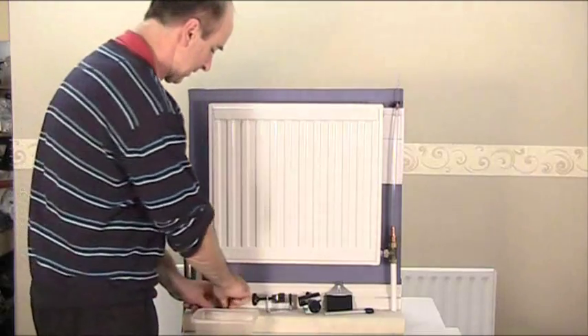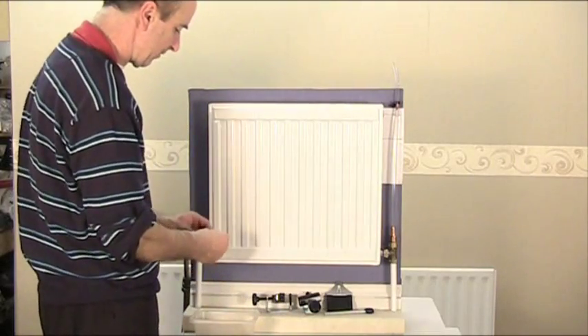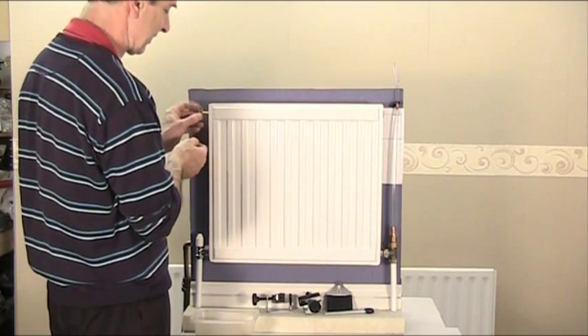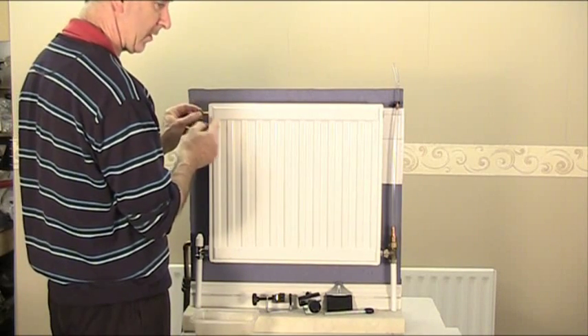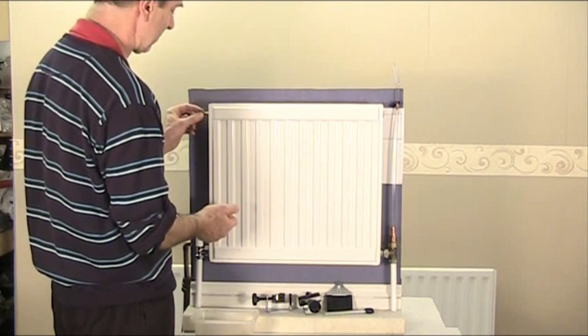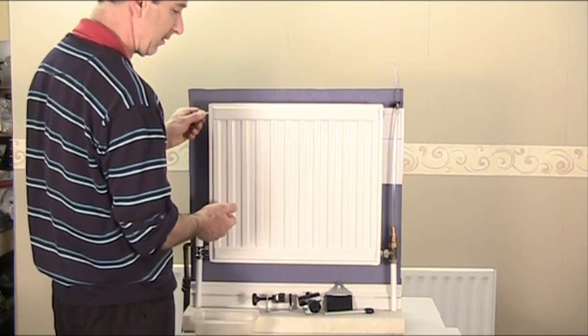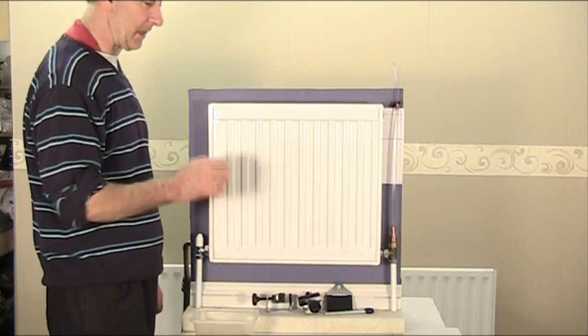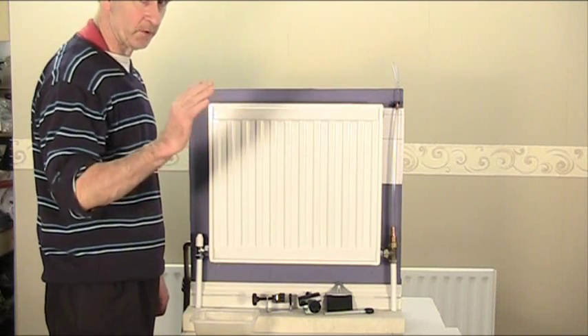So basically that's just a demonstration to show you what's happening when you are releasing air out of the radiator and the water is coming in. Now don't forget, it's a very important point that I mentioned there, which is on a sealed or pressurized system you must maintain the pressure in the boiler as you are bleeding the radiators, or the pressure will just drop to zero.